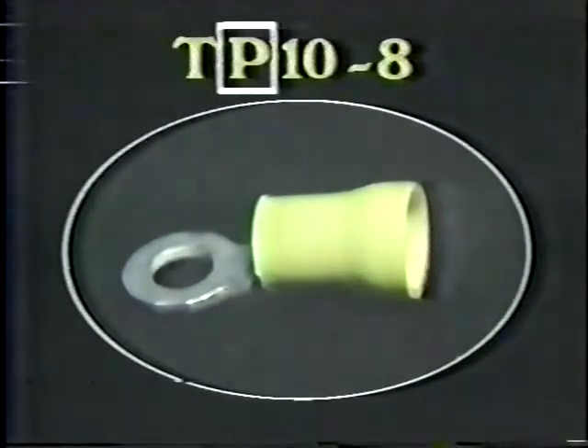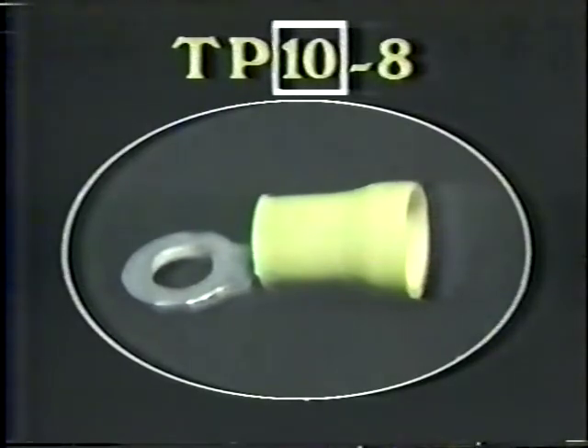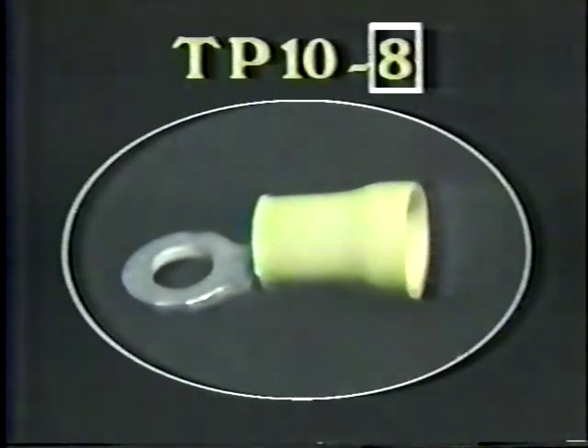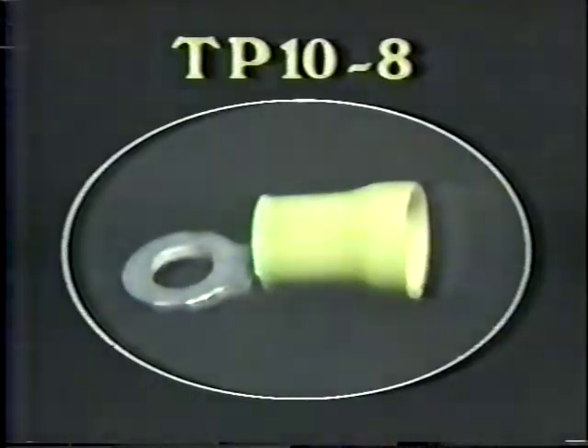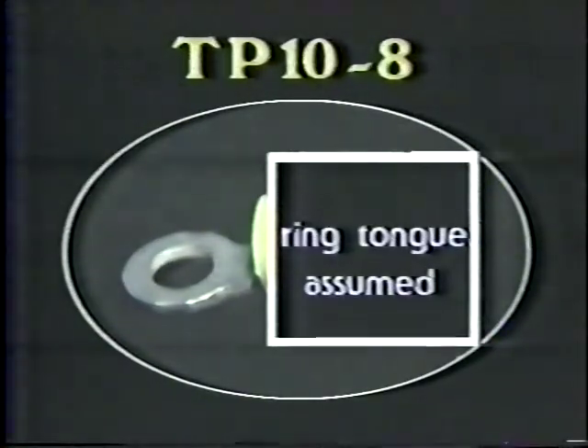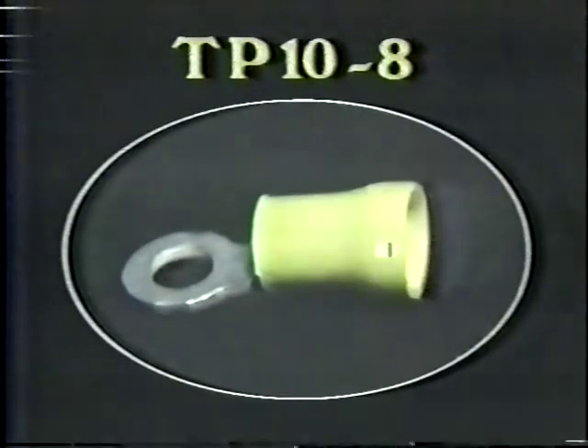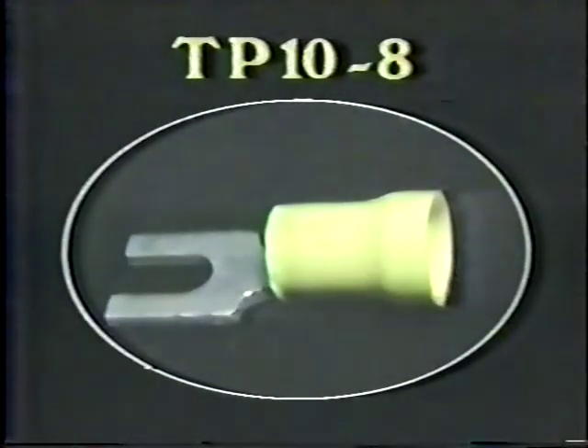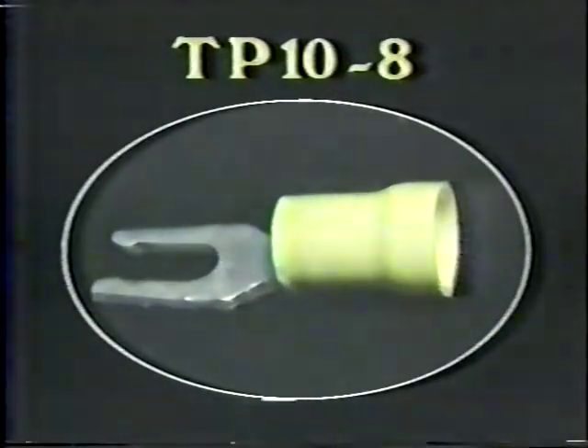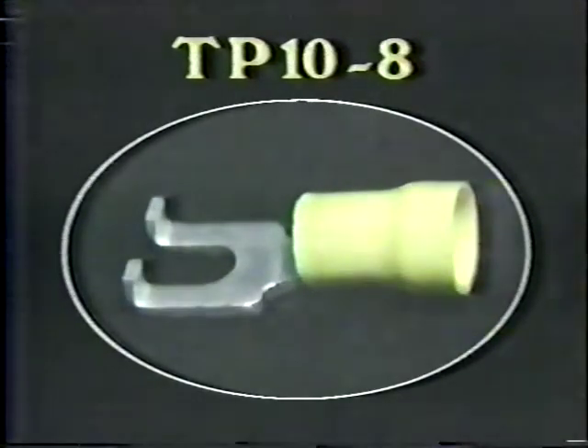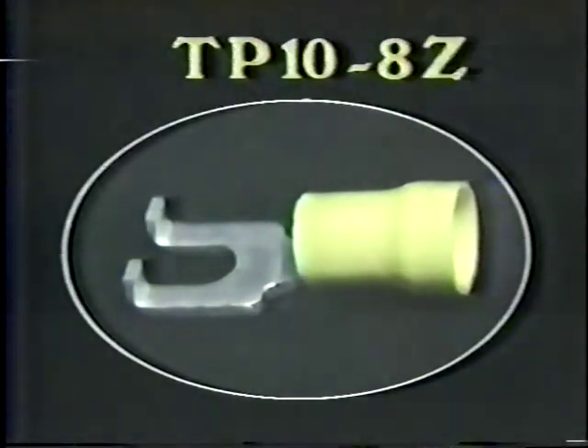Here we have a terminal with polyvinyl chloride insulation, which will accommodate number 12 through number 10 gauge wires. This terminal is designed for a number 8 stud. As with nylon terminals, a ring tongue is assumed if nothing else is specified. Burndy vinyl lugs, however, offer a wide variety of tongue variations, such as a fork tongue designated by the suffix F, a locking fork designated LF, and a flanged fork designated by suffix Z.